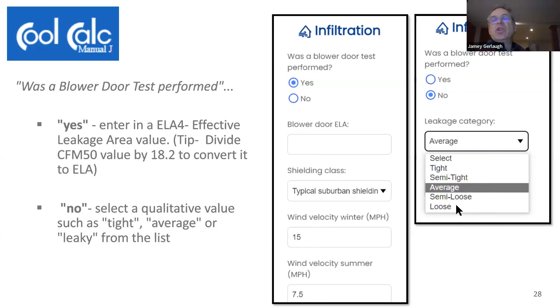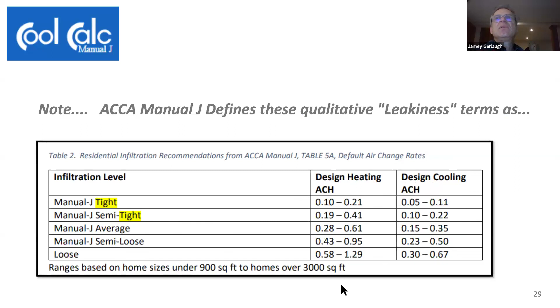If you don't have a blower door test, you click no, and you can put in this qualitative measure. This is a pull down screen where you can select tight, semi-tight, average, semi-loose, or loose. You're probably wondering how that corresponds in the real world - I don't know what semi-tight actually means myself. I found this in the Manual J manual, showing the corresponding air changes per hour that those qualitative terms refer to.